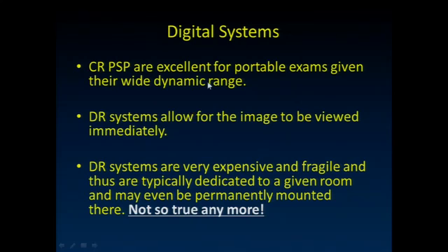CR, photostimulable phosphors, are great for portable exams. You take them up, image them, bring them back. They have a really wide dynamic range. Digital systems allow for the image to be viewed immediately at multiple locations. And we used to say CR was nice for those portables, you go up, shoot them, bring it back down, those kind of things.